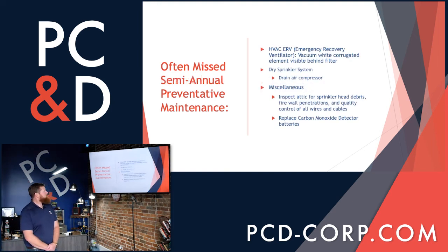And also, as we talked about the sprinkler systems for your dry systems, to keep that flapper valve that we mentioned beforehand in check is your air compressor. Something that Dave and I come across plenty of times in the field is that the excess moisture built inside these air compressors is not properly drained and therefore closes in on its life expectancy, and they go out far before they should. A couple of other items is always make sure your attic space is free of debris, cables. If any penetrations from one zone to the other are present, make sure you get those sealed up nice and tight. And carbon monoxide detector batteries, along with your smoke detectors, if you have a battery backup, should be changed every 6 months.